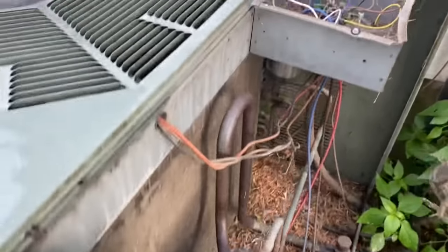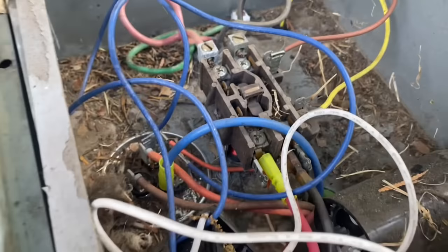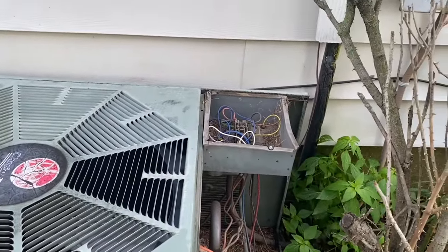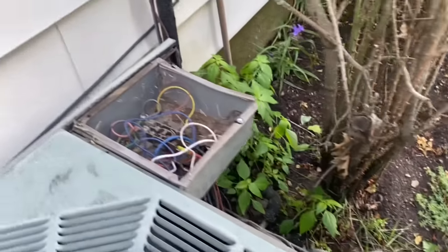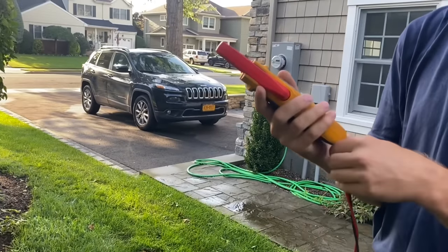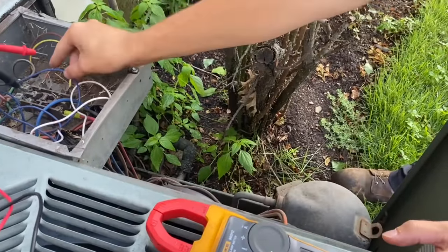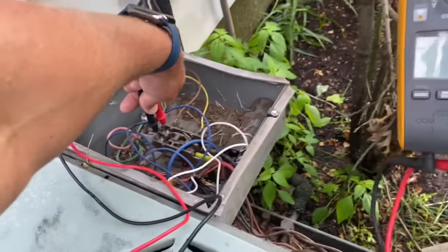Our contactor is now pulled in — she looks pretty charred right there. Let's get the voltmeter and check for voltage. Right now the contactor is pulled in. One thing I'm fearing is a tripped breaker. Set that to read AC volts — perfect. Now grab your two leads, put one right there and another one right there. We have nothing — nothing there.